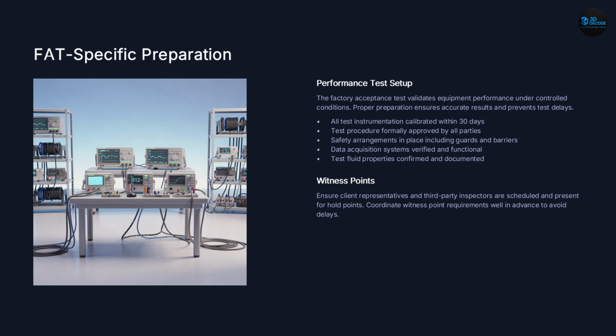All test instruments should be calibrated recently, typically within the previous 30 days. The test procedure must be formally approved. Safety arrangements must be in place. Guards, barriers, emergency procedures, and data acquisition systems must be verified. Because without accurate data, performance testing becomes meaningless.